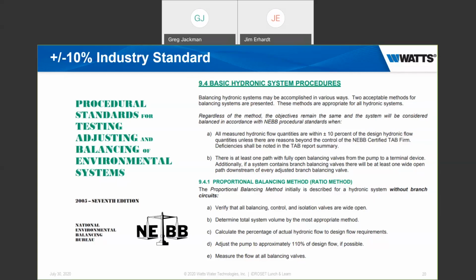So the bottom line is you can balance a system to plus or minus 5%, but most balancing contractors will push back on that to the specifying engineer because it is so time consuming to get to that level of accuracy. So the standard is 10%. And the iDROSET valve, as it comes out of the factory, is well within that plus or minus 10%. It is reading the flow directly. You are not calculating or estimating flow based on pressure drop. It actually reads the flow inside the valve. So that's where the plus or minus 10% comes from.